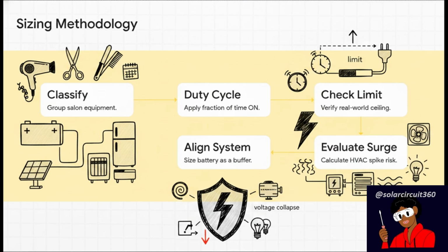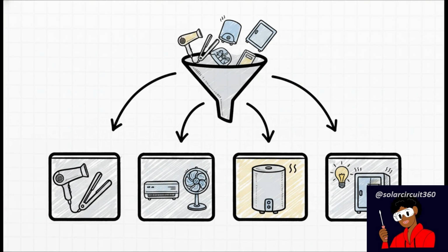And hey, here's a massive takeaway on that last point. In a behavioral system design, your battery isn't just energy storage, it's a critical shock absorber. It buffers those simultaneous heat loads, the compressor startup events, and short-term clustering. If your battery buffer is too small, the system voltage literally collapses before the protection circuitry even has time to react. Let's quickly detail that very first step.